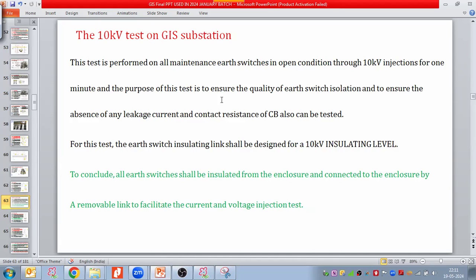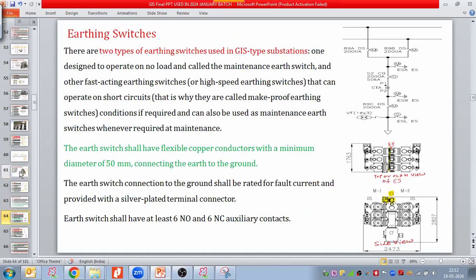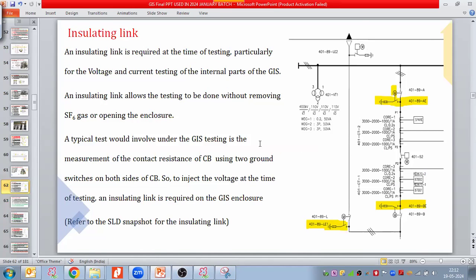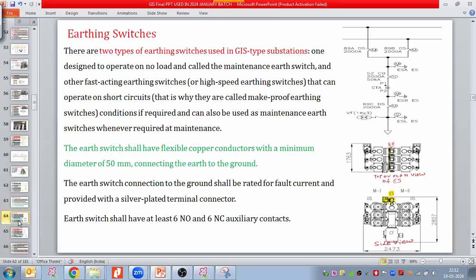to ensure the absence of any leakage current, and the breaker contact resistance testing also can be tested with the help of this 10 kV test. For this test, the earth switch insulating link shall be designed for 10 kilovoltage insulating level. To conclude, all earthing switches shall be insulated from the enclosure and connected to the enclosure by a removable link to facilitate the current and voltage injection test in the GIS module. So due to that reason, we provide the insulating link with the earthing switch, and when we prepare the SLD, make sure it is given.